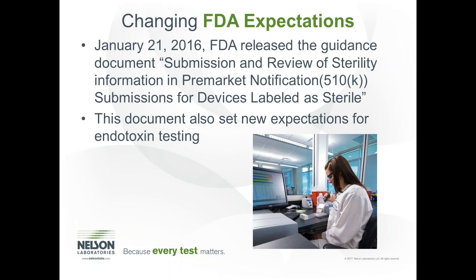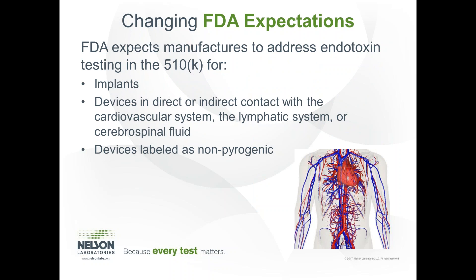There are a few things that are changing in the industry. As of January 2016, FDA released the guidance document, 'Submission and Review of Sterility Information for Premarket Notification 510(k) Submissions for Devices Labeled as Sterile.' This document caught many manufacturers off guard because, even though it was for devices labeled as sterile, it set new expectations for endotoxin testing. This was particularly impactful to implant manufacturers, as historically implants were exempt from USP 161. However, FDA now recognizes risk associated with that exemption and is requiring endotoxin testing for implants, in addition to devices in direct contact with the circulatory system, lymphatic system, or cerebral spinal fluid, and devices labeled as nonpyrogenic.